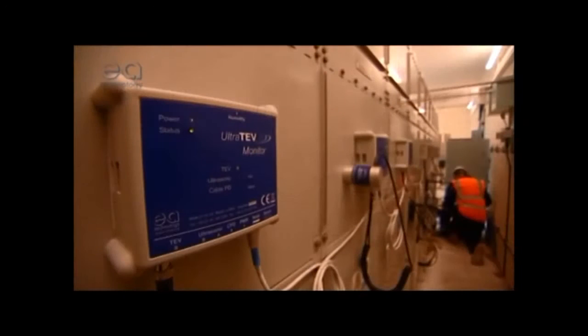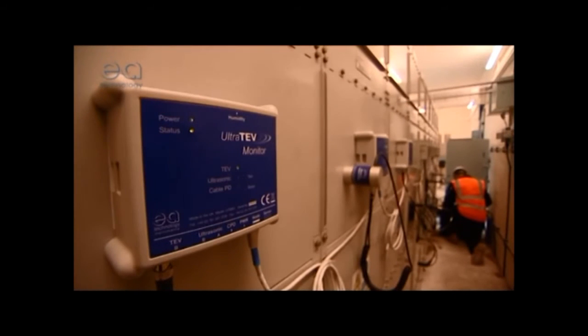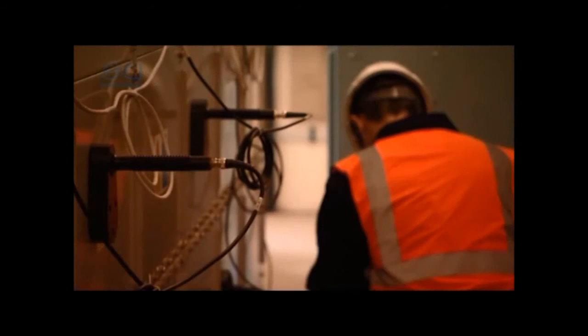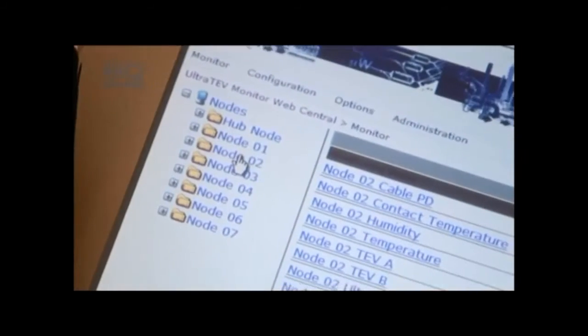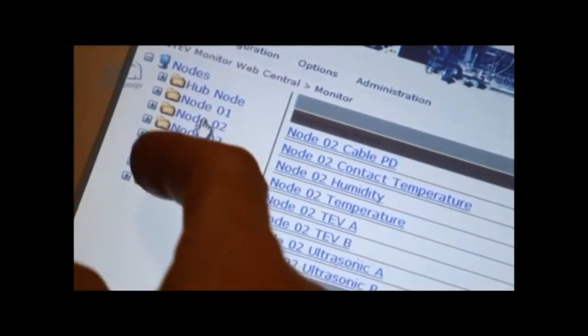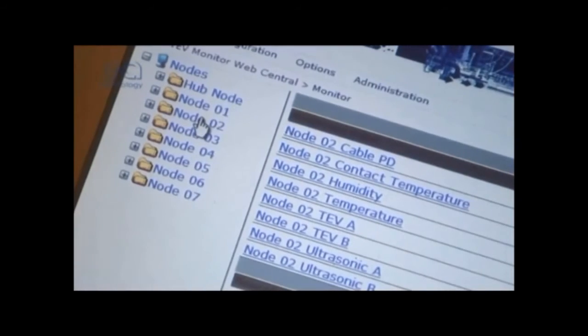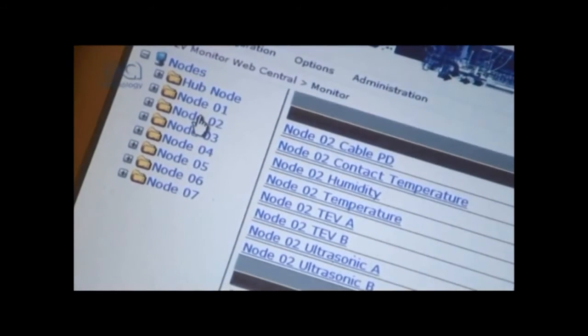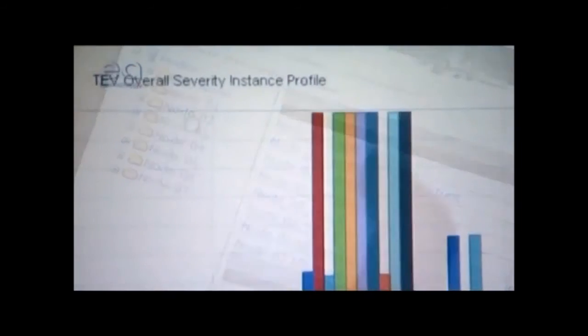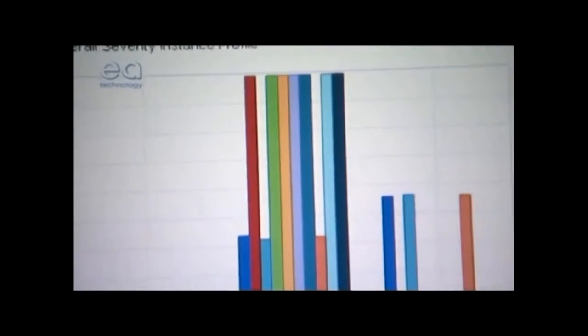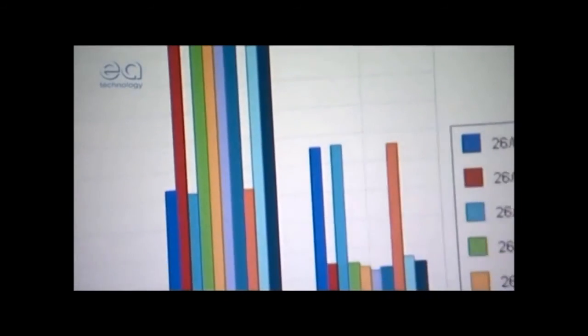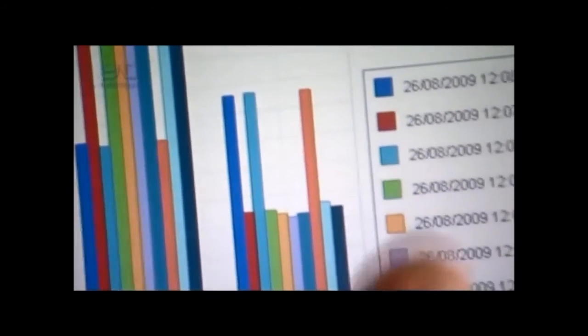It continuously measures PD activity non-intrusively. It uses time-of-flight measurement to locate PD activity to within 30 centimeters. It measures PD activity at up to 250 points simultaneously. It records PD activity over time.